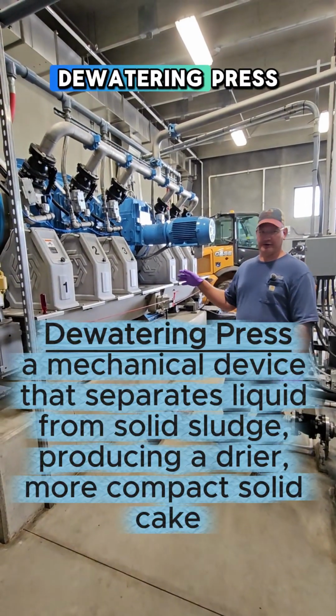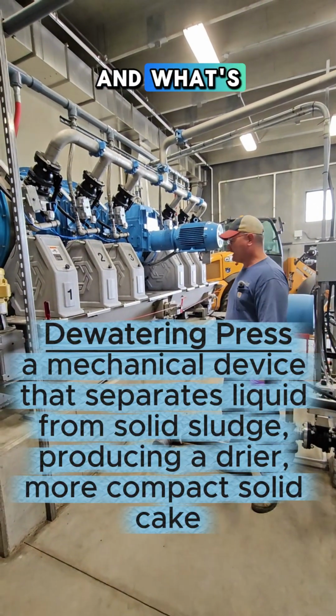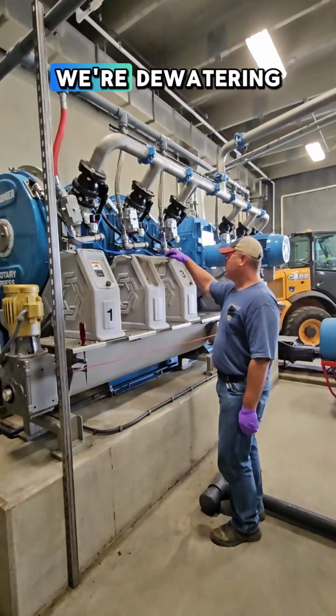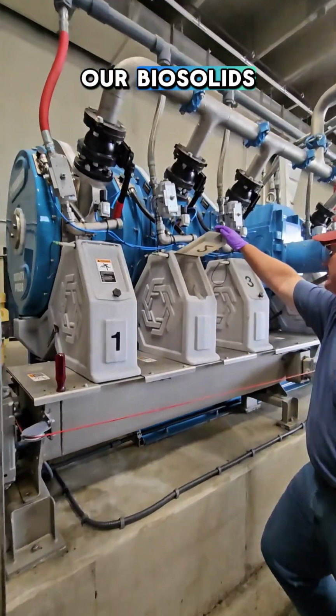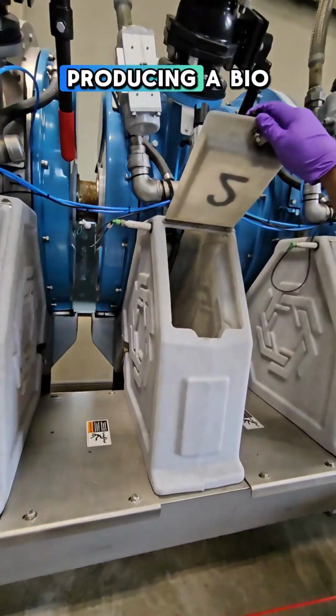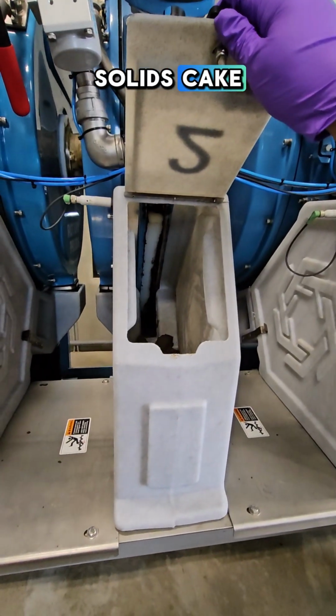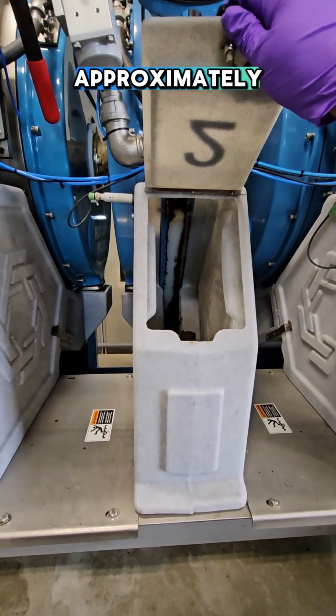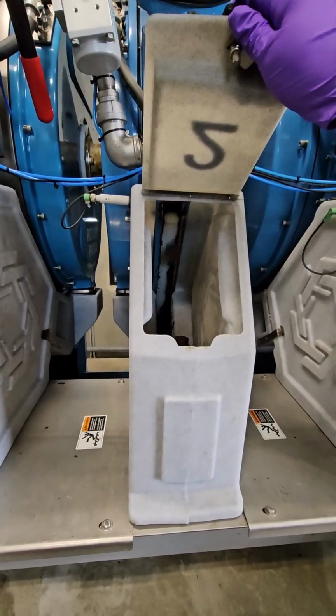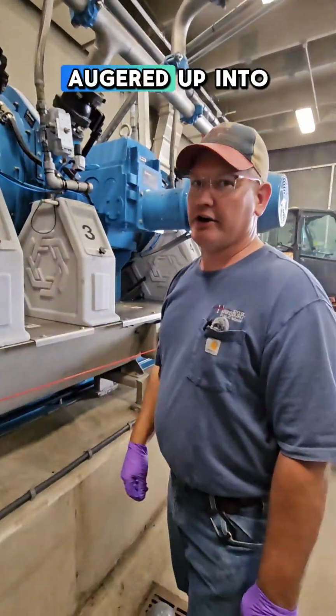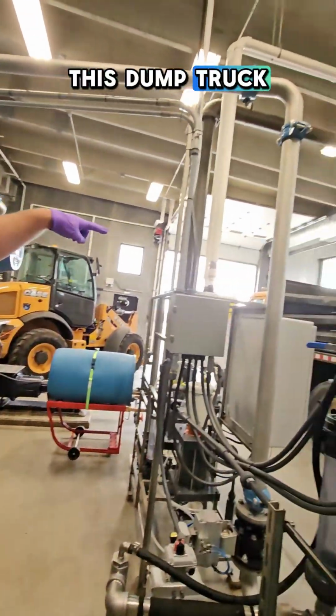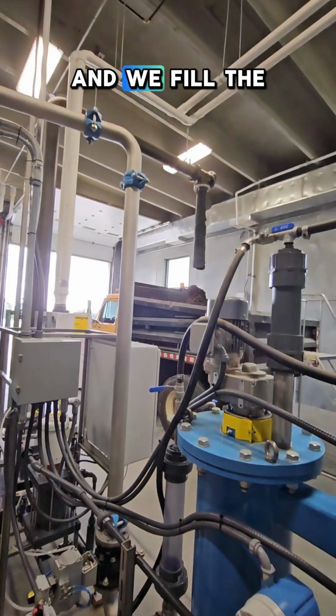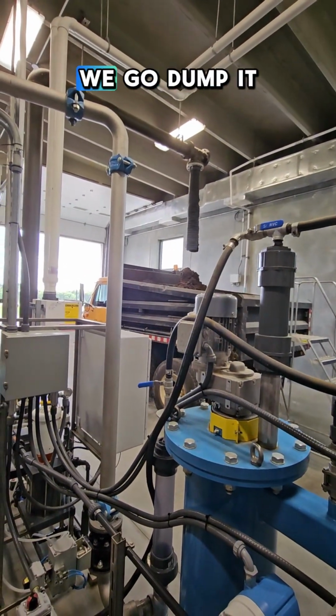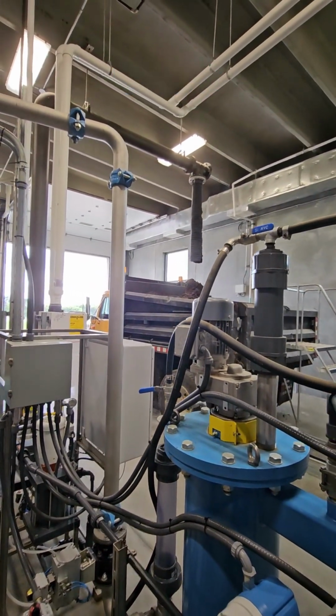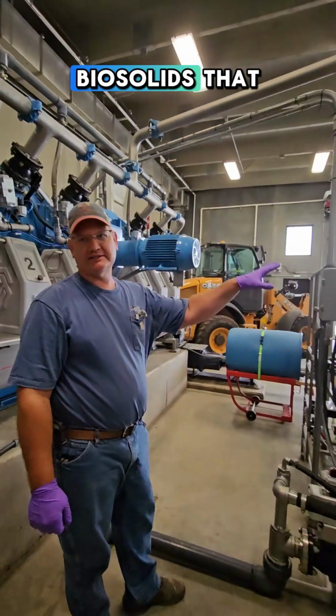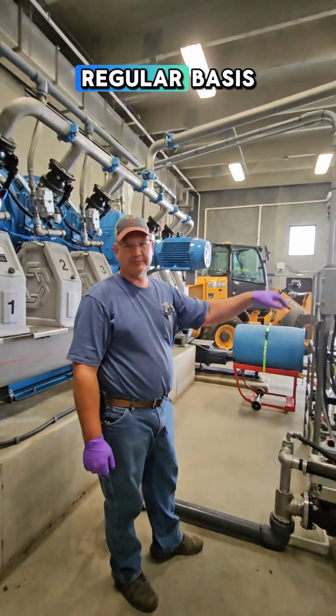So this is our dewatering press. What's happening here is we're dewatering our biosolids, and we are producing a biosolids cake that is approximately 13% solids, and that is getting augured up into this dump truck. And we fill the dump truck, and at the end of the day, we go dump it in our storage facility. Those are our biosolids that the treatment plant produces on a regular basis.